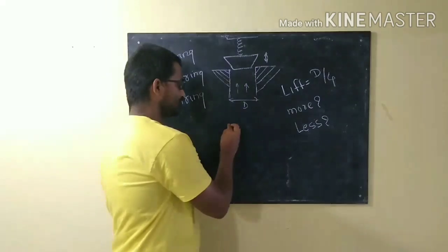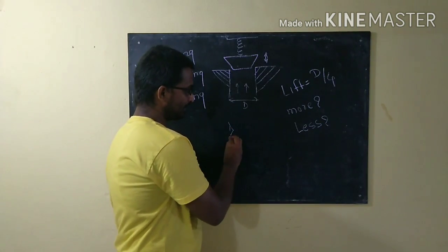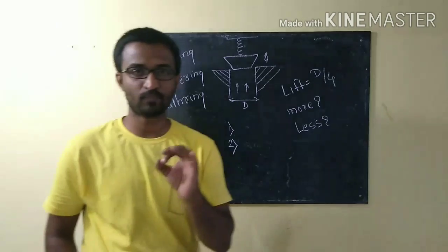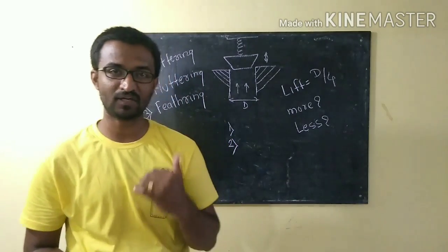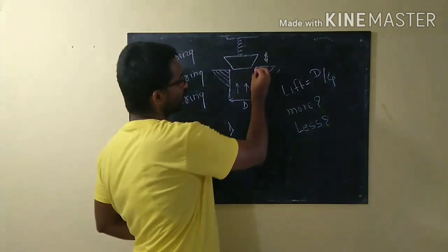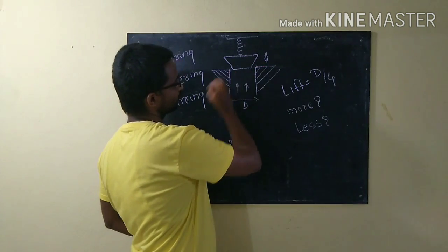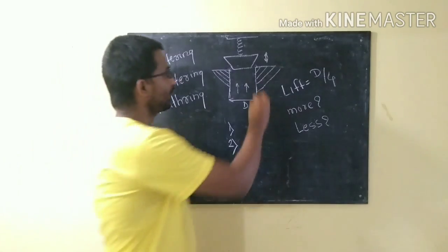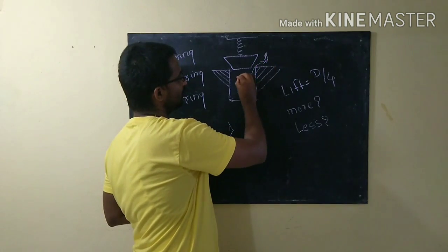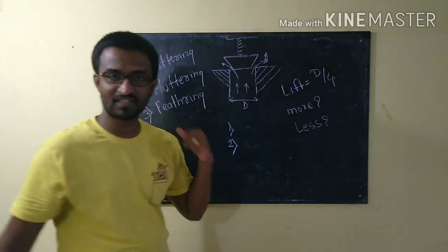This is the first reason. In the second reason, if you are not using proper boiler water, and it has sediments and other impurities, those impurities get accumulated over here. Because of that, a thin film of steam leaks from here. This leakage is called feathering.